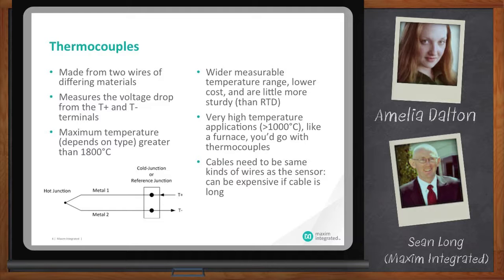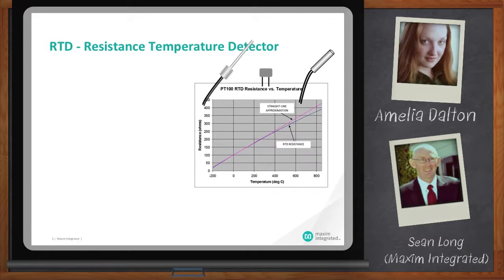So the other type is called an RTD or resistance temperature detector. Typically, there's two popular types, the PT100 or PT1000. Okay. And the number refers to essentially the resistance at zero degrees C. Ah, all right. And as you can see, as the temperature changes, the resistance varies and this is relatively linear and from this, we're able to deduce what the temperature change has been.